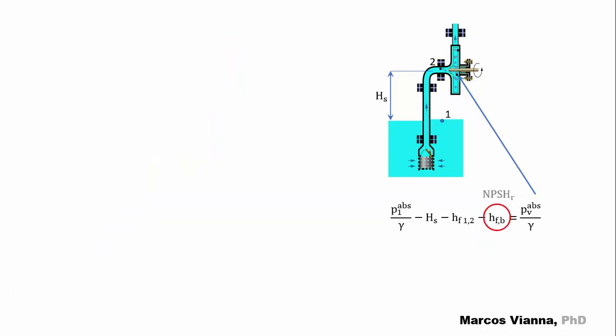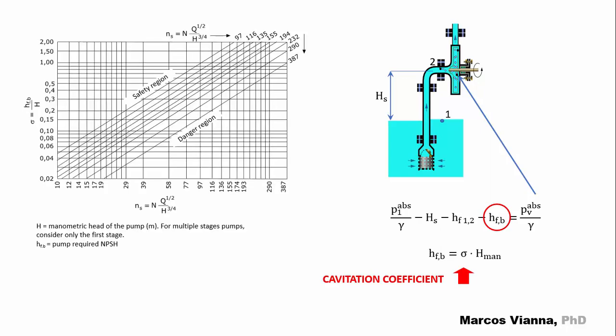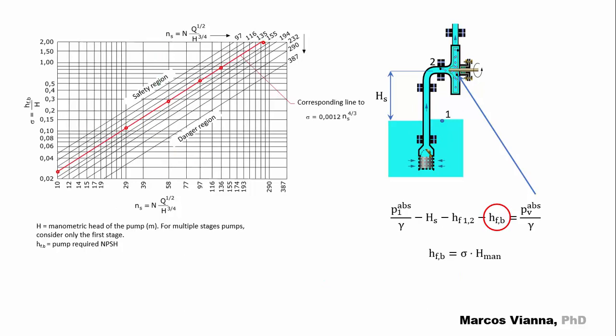Let's start with a small change in our nomenclature. We'll use HFB instead of NPSHR to represent the required NPSH. We can find its value by multiplying the manometric head by sigma, which is the cavitation coefficient. Finding its value can be tricky. This diagram shows where we can safely operate the pump if we want to prevent cavitation. For this purpose, we must calculate the specific speed of the pump and try to avoid the danger region. This line is usually safe for practical purposes, so let's use it in our example.